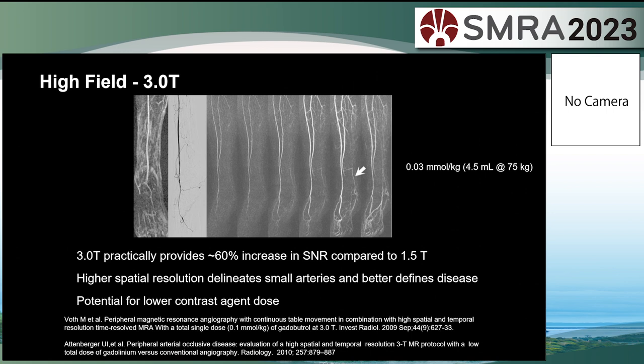3 Tesla gives us more SNR compared to 1.5T — maybe not quite as much as we'd hoped, but more nonetheless. This allows higher spatial resolution, better-defined smaller arteries, and there's also the potential for lower contrast agent dose for the same image quality.